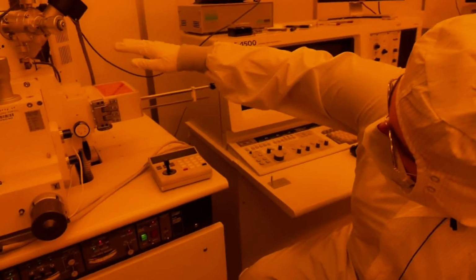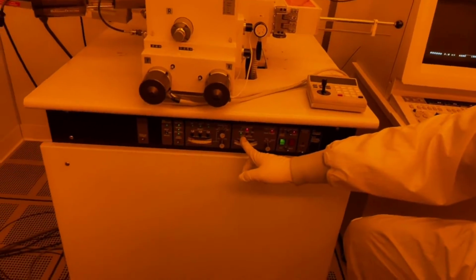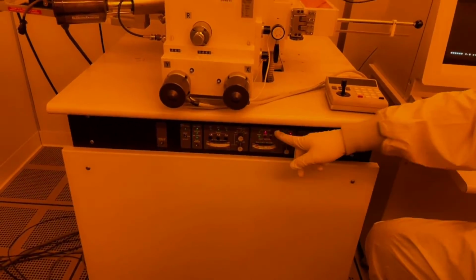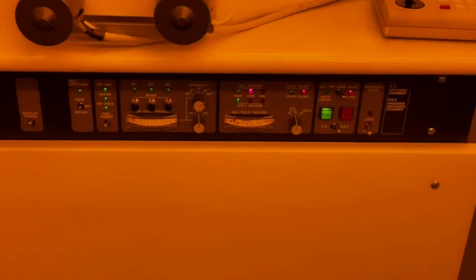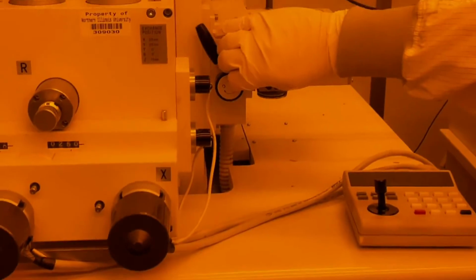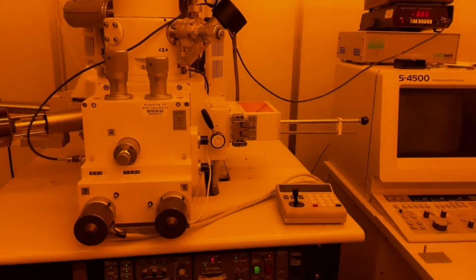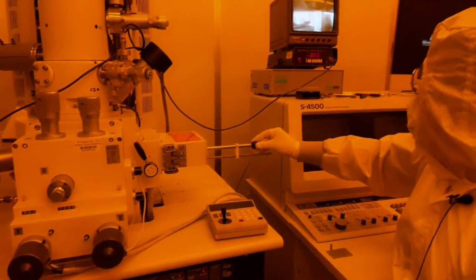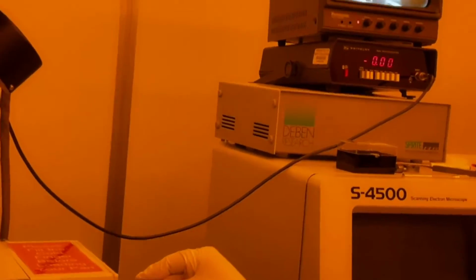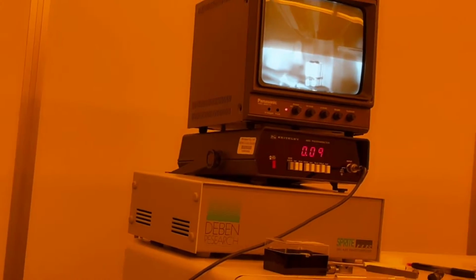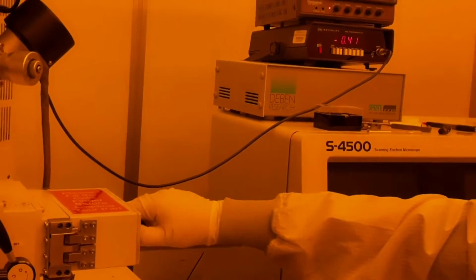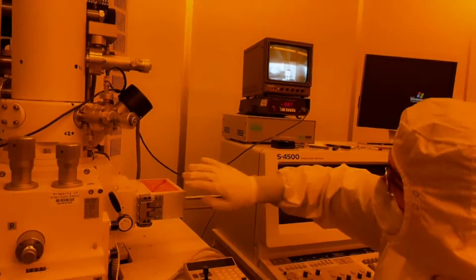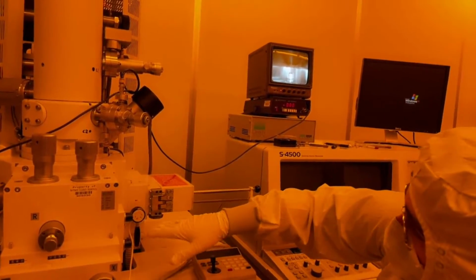So, as you can see, our sample exchange chamber has reached high vacuum. We just want to make sure the sample chamber is also at high vacuum before we start the gun. But now we are able to perform the sample exchange. So we gently slide it in. It locks into place on our sample stage. We unscrew the exchange rod, pull it back out, and then we close our valve.